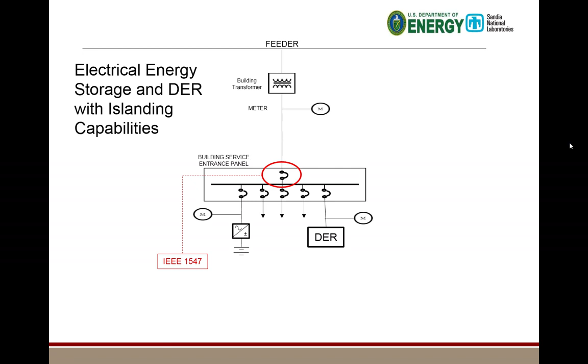So some project considerations in the design. You need to understand what applications you want to use your energy storage for, and design it appropriately. You want to optimize how big the size and power rating is and for how long you really need it to do your job. Some technologies are better suited for long durations and others for short durations. You need to worry about the control. It's going to get probably a little tricky when you're trying to control distributed energy resources and energy storage. You like to see one master controller controlling all components. And also, one thing that's not talked about a lot is utilizing your energy storage to offset any fuel generation, decreasing your fuel consumption. And then with many of the newer systems, they're still working on the UL listing.